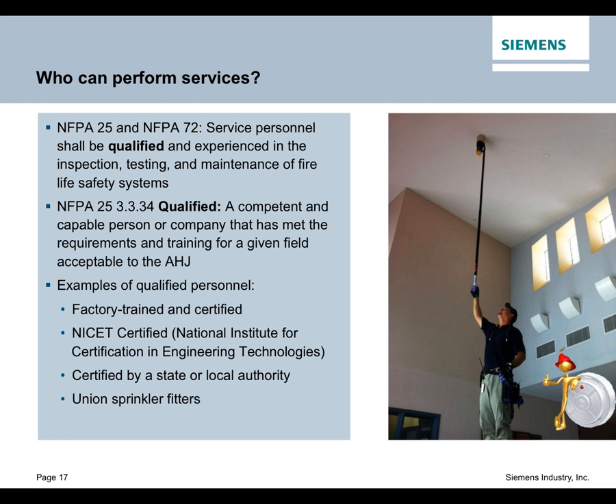NICET certification, the National Institute for Certification of Engineering Technologies, is an excellent resource. This is a third-party testing agency that creates criteria in order to certify individuals based on the successful passing of a test on the given competencies for a level that they will be given in order to provide execution in the inspection and testing world. So there are NICET certifications for fire sprinklers. There's NICET certifications for fire alarms, as there are for other building components, but those are the two we're focused on here. And that's probably the most popular one today.